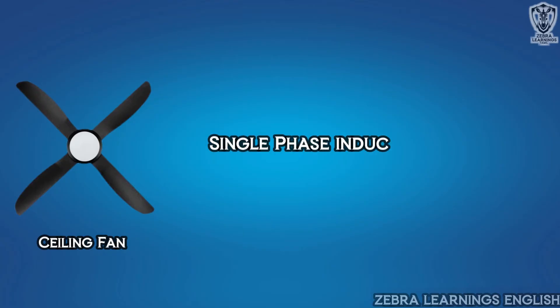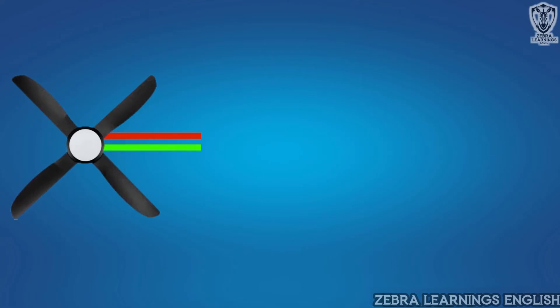Single phase induction motor is used in ceiling fan. This motor has two coils. One of them is starting coil, and the other is running coil. One terminal is taken from these two coils, and it is connected inside the motor, and given as common terminal.